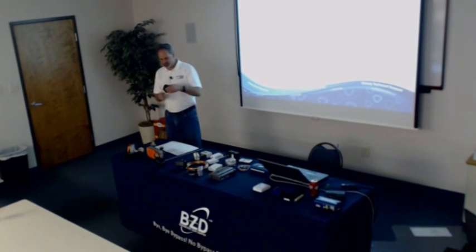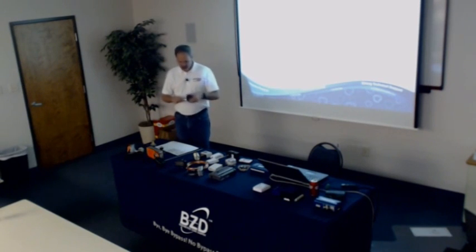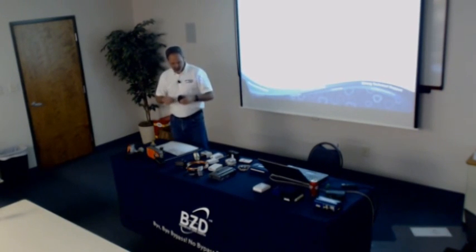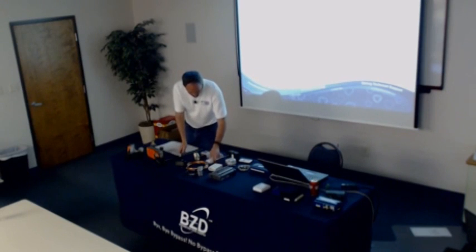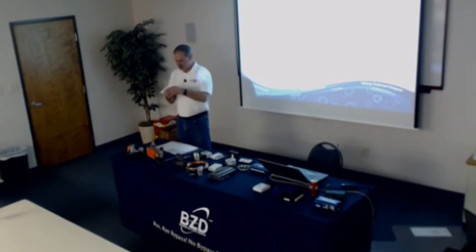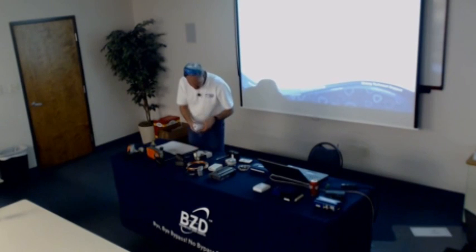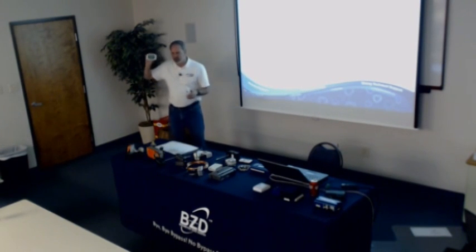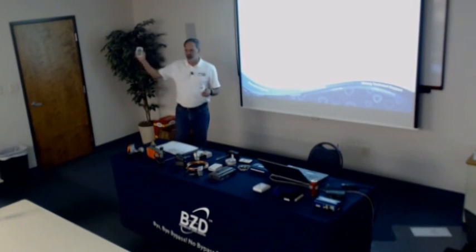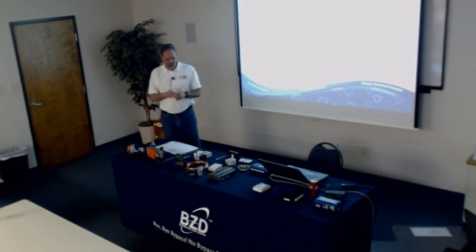This one's an immersion sensor. Happens to have a well screwed onto it. Screw that guy into the pipe. So you can just take your sensor, screw it on, run your wires inside. It's exactly the same. It's 10,000 ohms at 77 degrees. Easy to check, inexpensive. You know, a regular room sensor like this. This one's actually humidity. A room temperature sensor like this guy, you know, it's less than 30 bucks. And you can get them with any flavor you want. This one's just a temperature sensor with an override button on it, but you can get them with a set point.